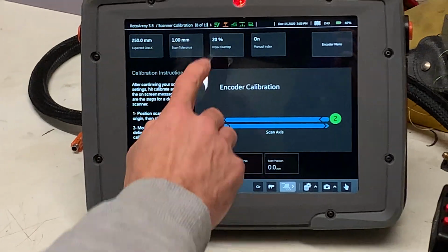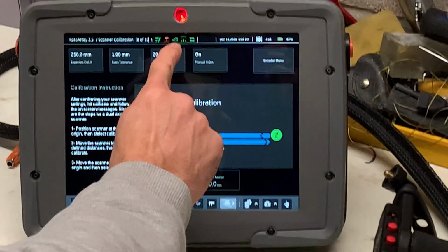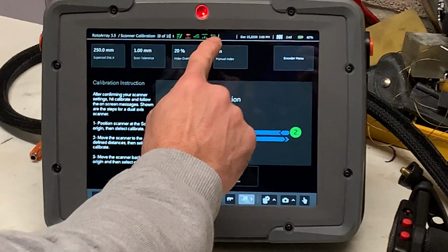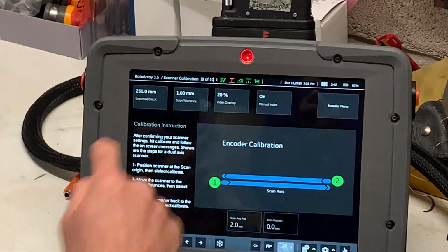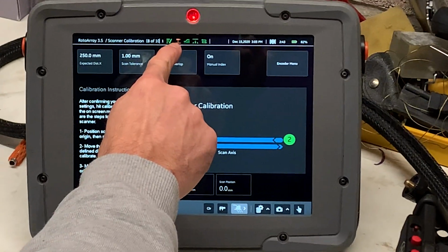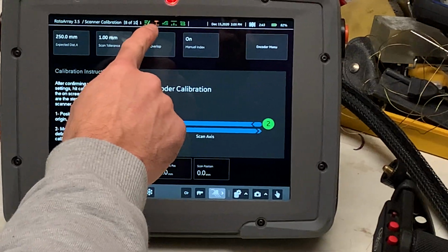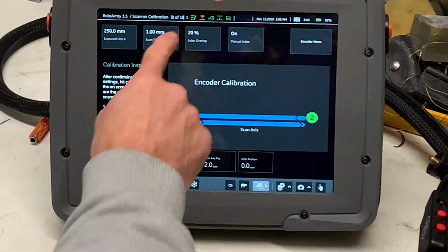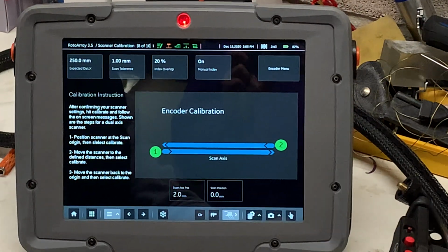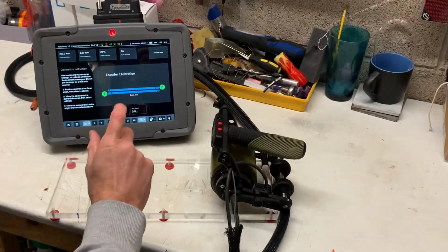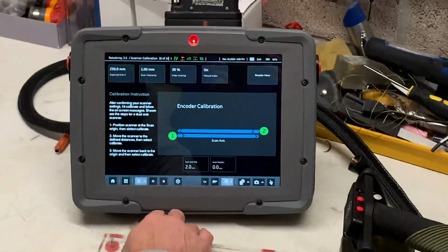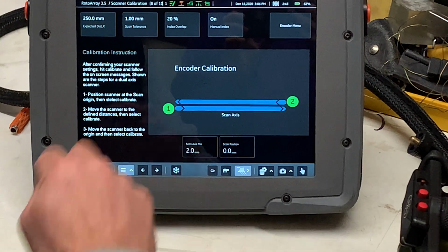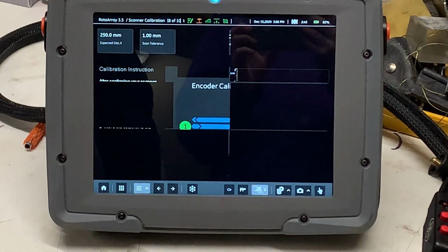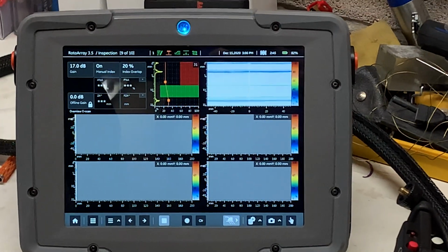So all the time we've been doing these things, the dead element check, the velocity, the TCG and the scanner, these things have been going from orange to green. So this one here at the top is still orange because we didn't do a delay calibration. And the reason being is we've got this water path and we've got the IF gate monitoring it, so we didn't need to do that. So everything's set up now. So the last page then, we move on to it, is the scan.